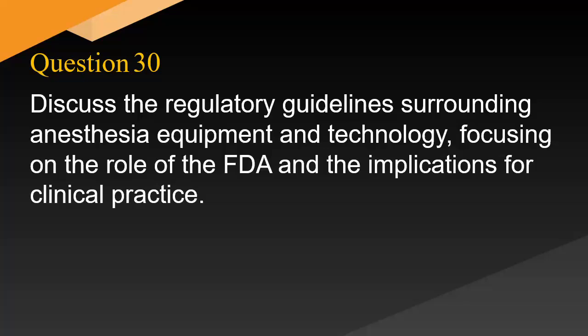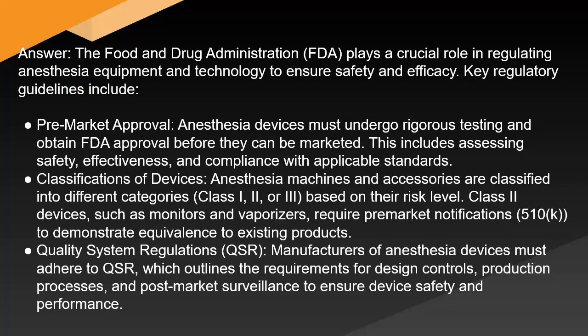Discuss the regulatory guidelines surrounding anesthesia equipment and technology, focusing on the role of the FDA and the implications for clinical practice. Answer: the Food and Drug Administration (FDA) plays a crucial role in regulating anesthesia equipment and technology to ensure safety and efficacy. Key regulatory guidelines include pre-market approval. Anesthesia devices must undergo rigorous testing and obtain FDA approval before they can be marketed. This includes assessing safety, effectiveness, and compliance with applicable standards. Classifications of devices. Anesthesia machines and accessories are classified into different categories, Class I, II, or III, based on their risk level. Class II devices, such as monitors and vaporizers, require pre-market notifications (510(k)) to demonstrate equivalence to existing products.